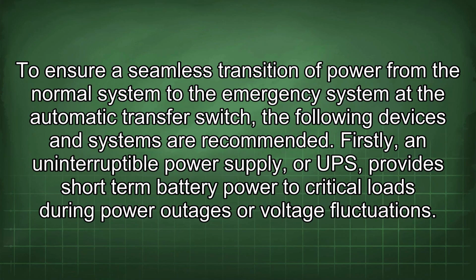To ensure a seamless transition of power from the normal system to the emergency system at the automatic transfer switch, the following devices and systems are recommended. Firstly, an uninterruptible power supply, or UPS, provides short-term battery power to critical loads during power outages or voltage fluctuations.